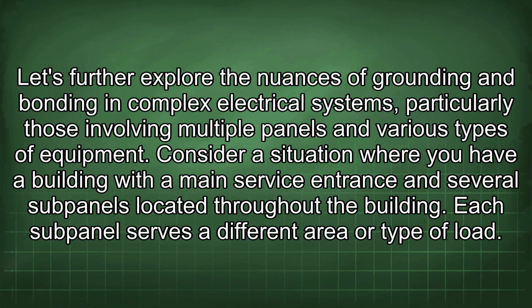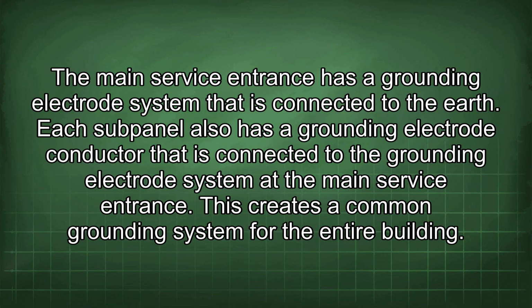Consider a situation where you have a building with the main service entrance and several subpanels located throughout the building. Each subpanel serves a different area or type of load. The main service entrance has a grounding electrode system that is connected to the earth. Each subpanel also has a grounding electrode conductor that is connected to the grounding electrode system at the main service entrance. This creates a common grounding system for the entire building.